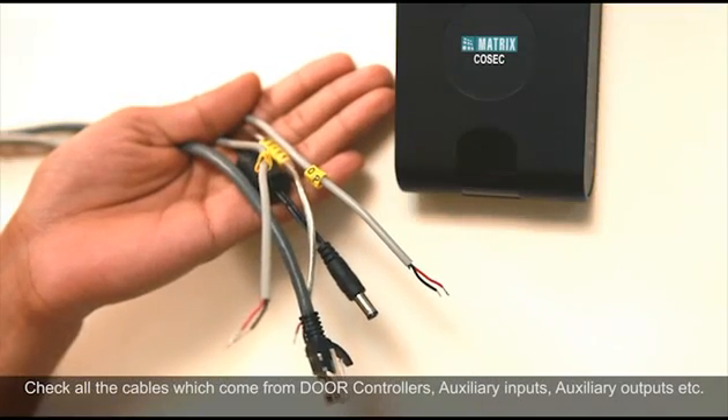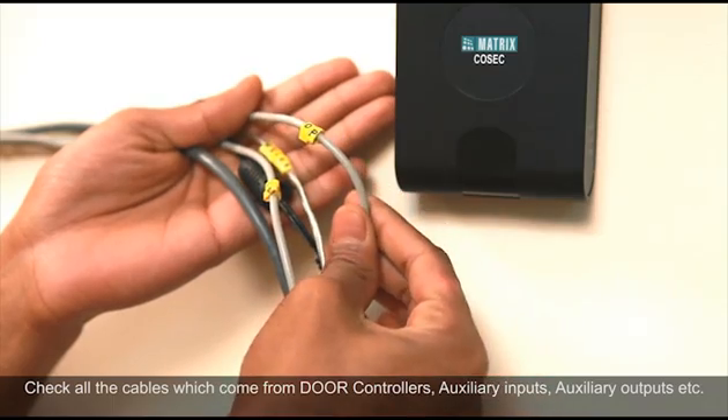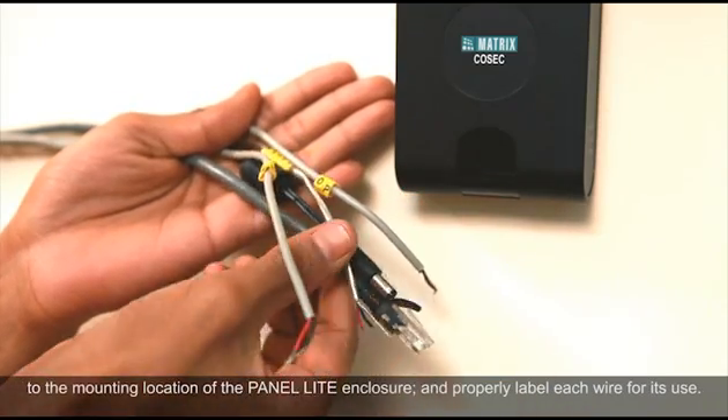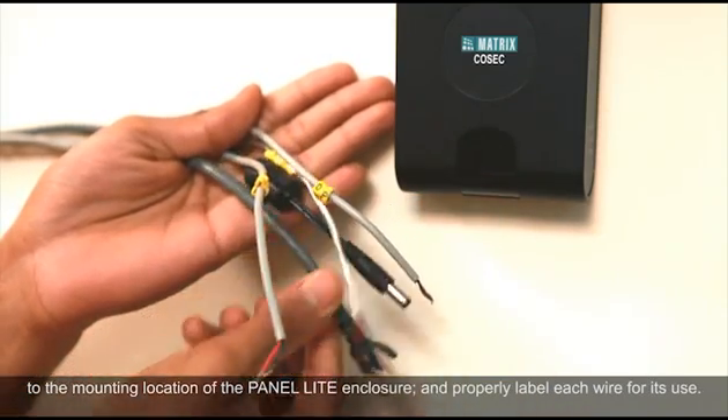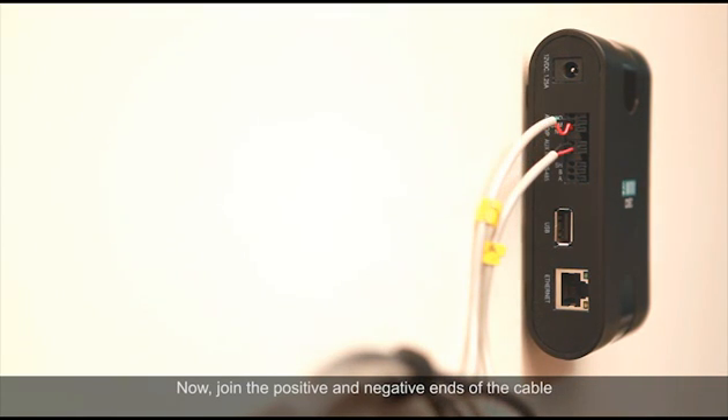Check all the cables which come from door controllers, auxiliary inputs, auxiliary outputs, etc. to the mounting location of the PANEL LITE enclosure, and properly label each wire for its use. Connect the NO, NC and COM conductors of this cable to the auxiliary output like hooter or siren according to the markings on the enclosure. Now join the positive and negative ends of the cable from the auxiliary input as per the print marks.